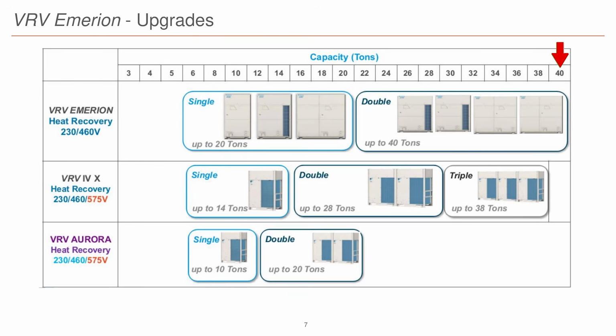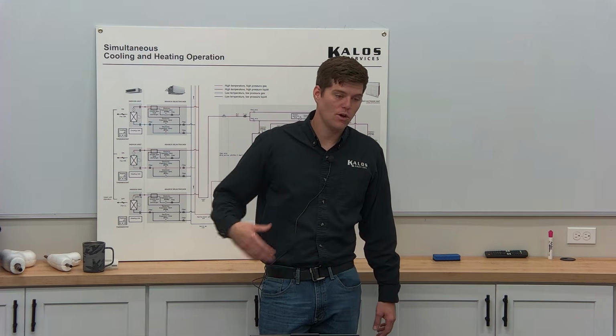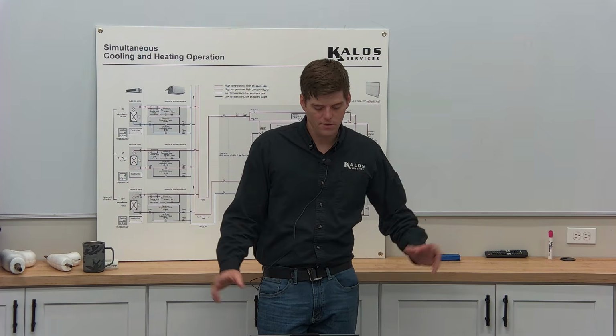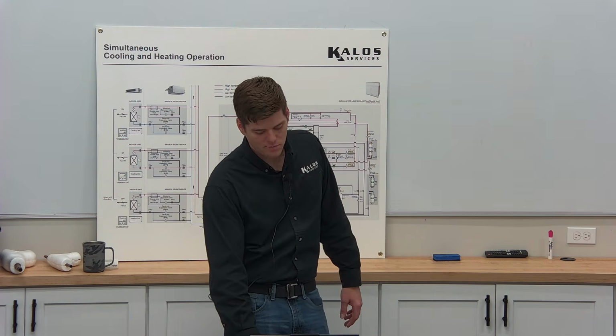So I can take 2 VRF condensers and put them side by side to replace 40 tons worth of capacity on a split system. And as you see, as we go up in tonnage, the cabinet sizes get bigger, you have more outdoor units, they'll all be tied together, they all work together. In a series of 3 outdoor units, one is going to be in charge, the other ones are going to follow that one's orders. That's how all VRF systems are. Doesn't matter the brand, doesn't matter the manufacturer, someone has to be in charge.